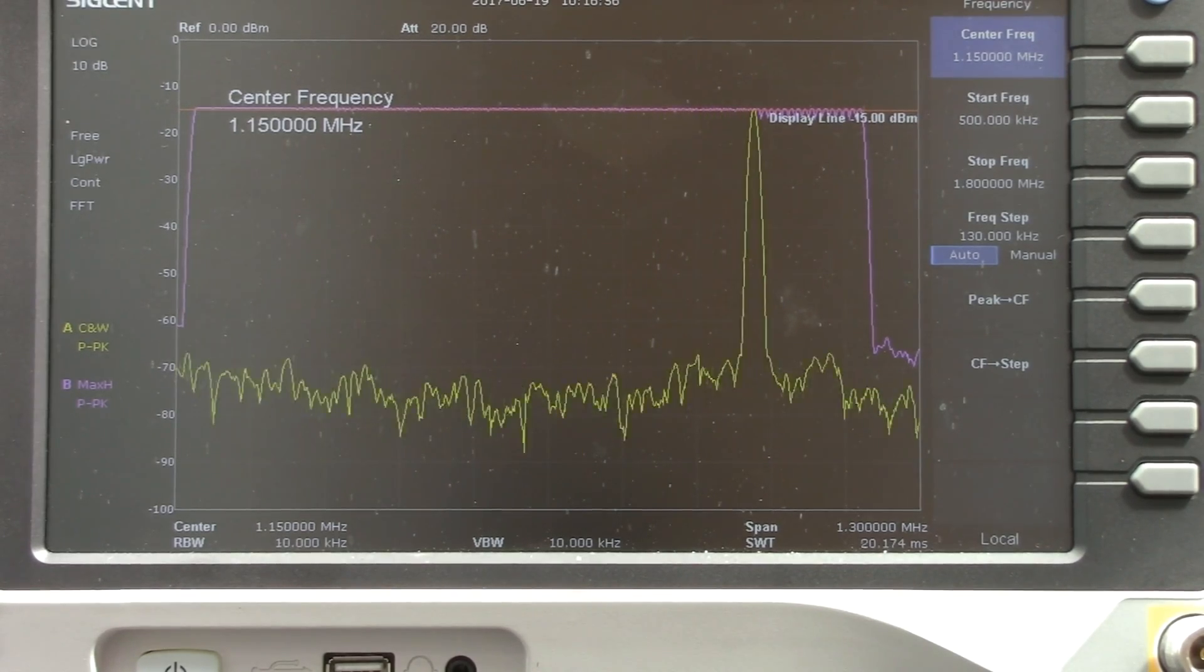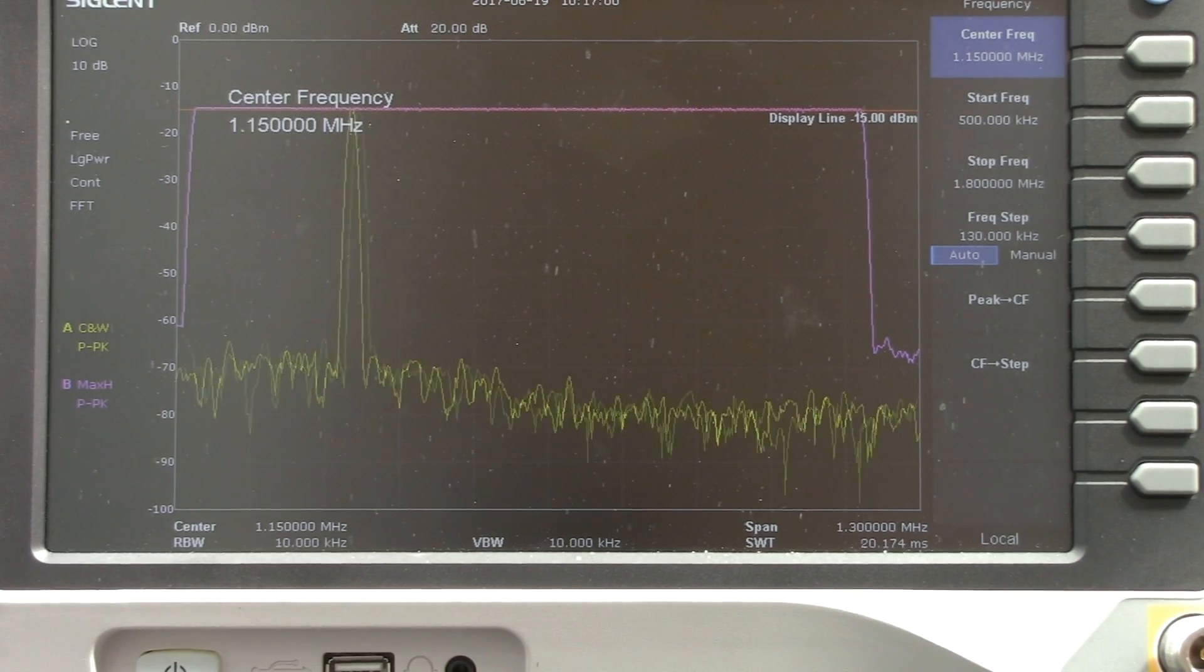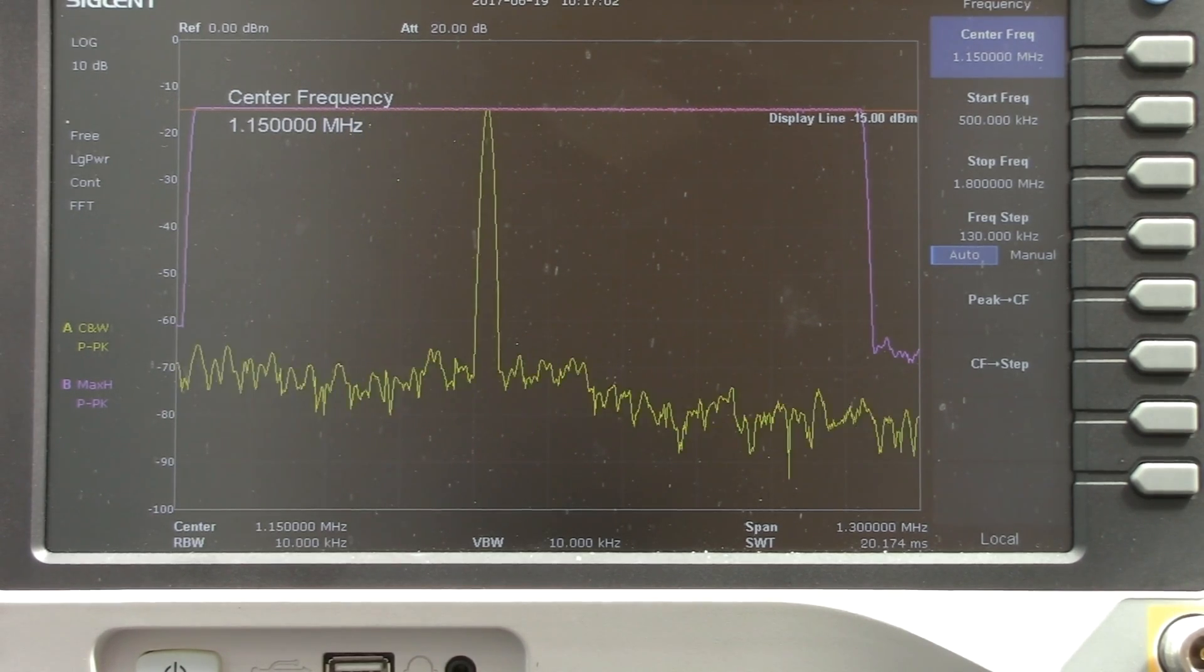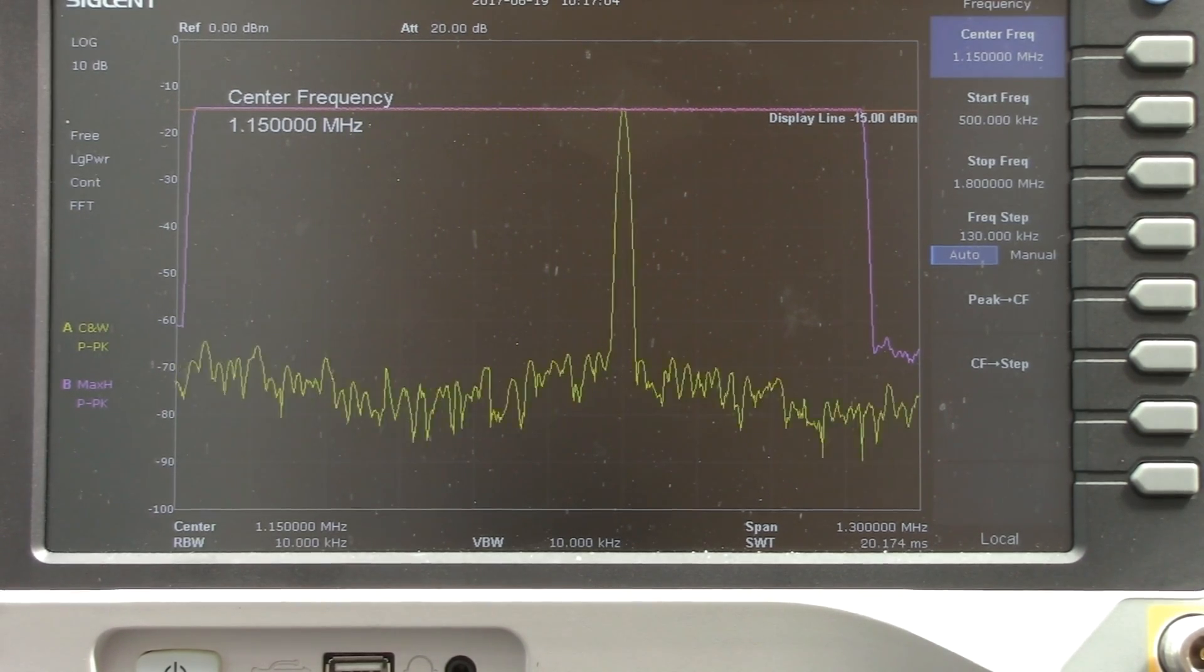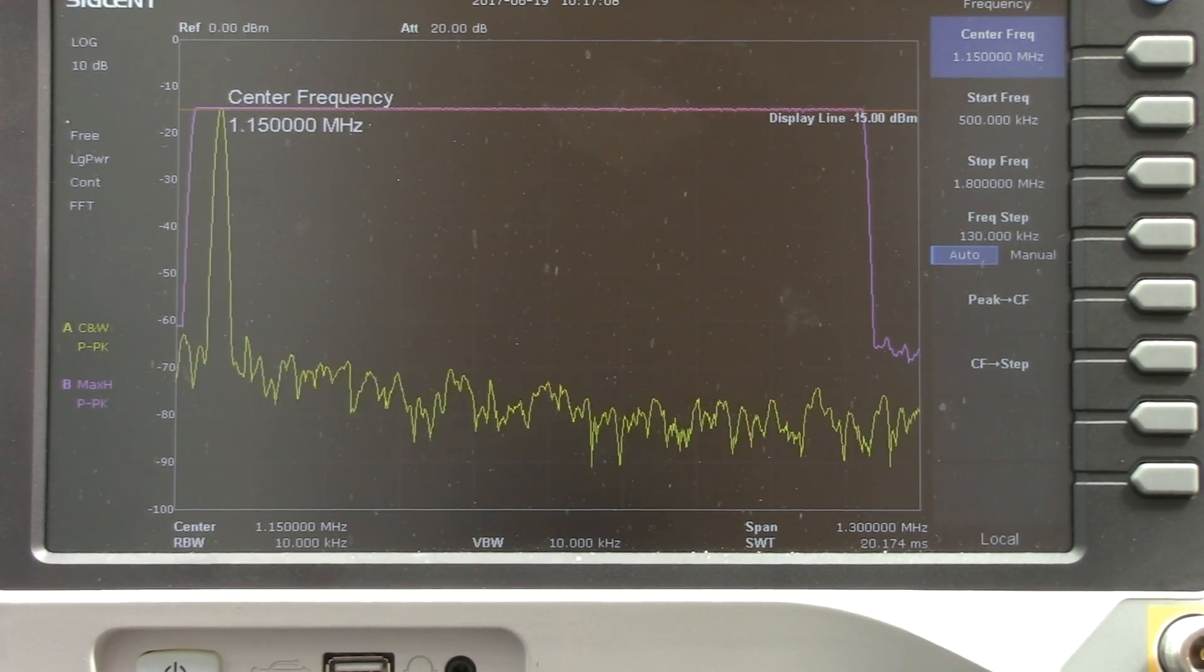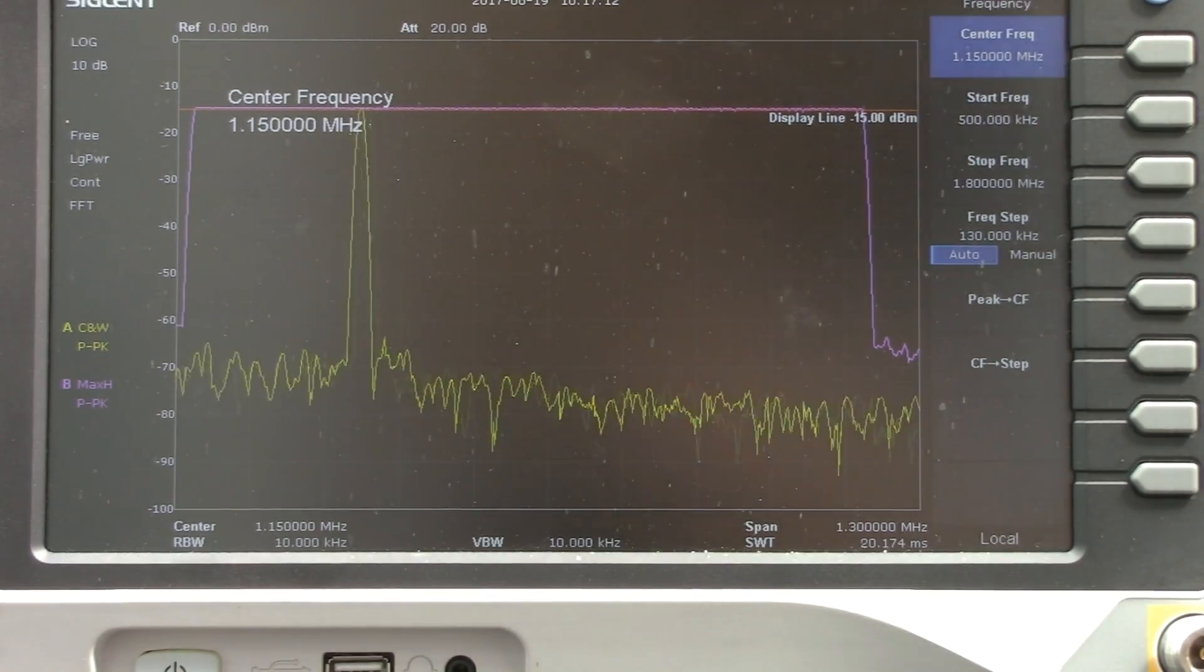And that pink is going to show us the max value in the max hold trace mode for this particular setup. And here now we're going to adjust the amplitude of the generator to minus 50 dBm here. I'll let that do a few successive scans. Take a closer look at the settings.